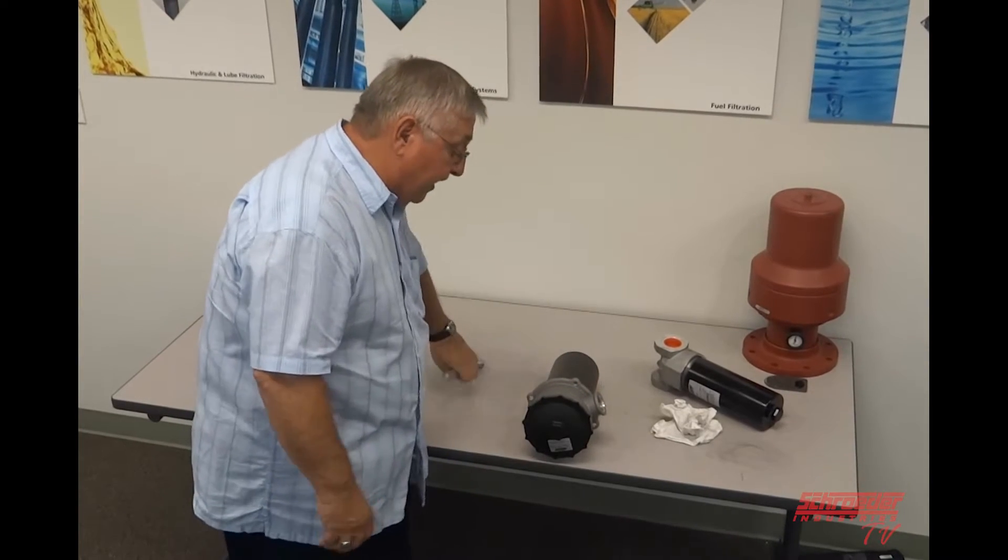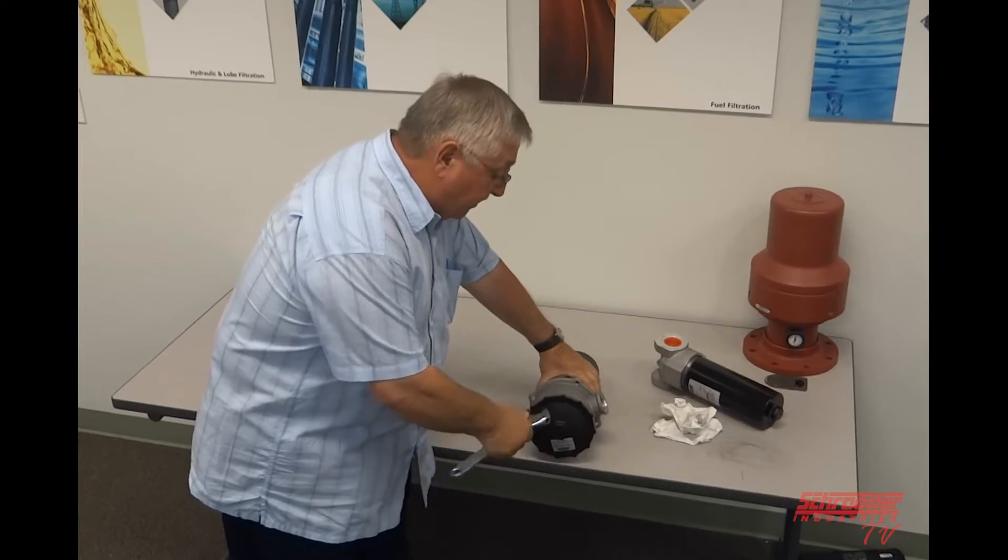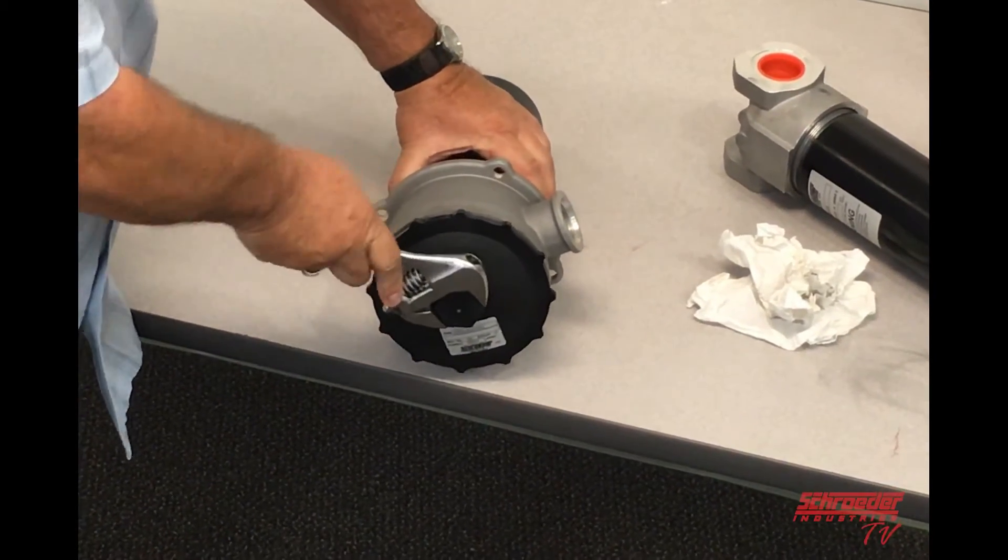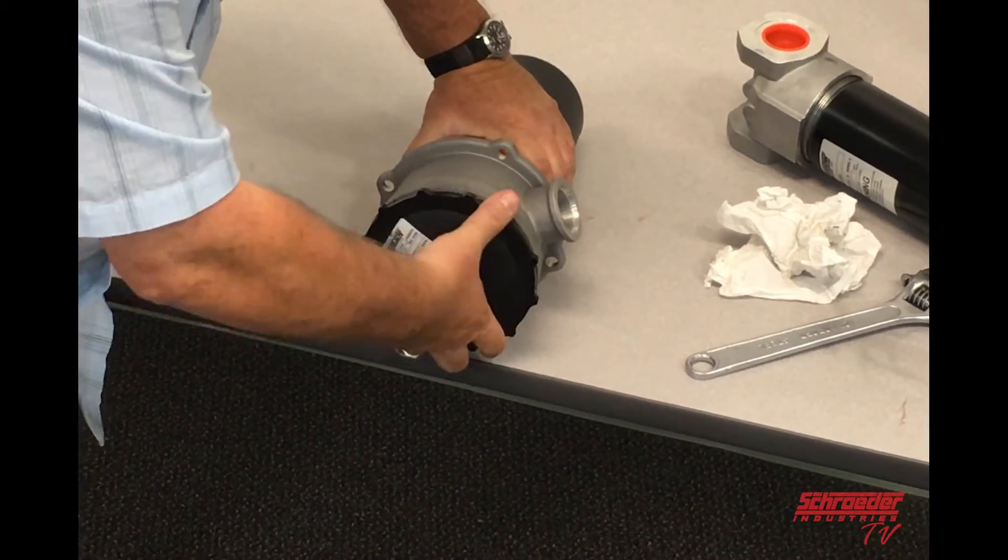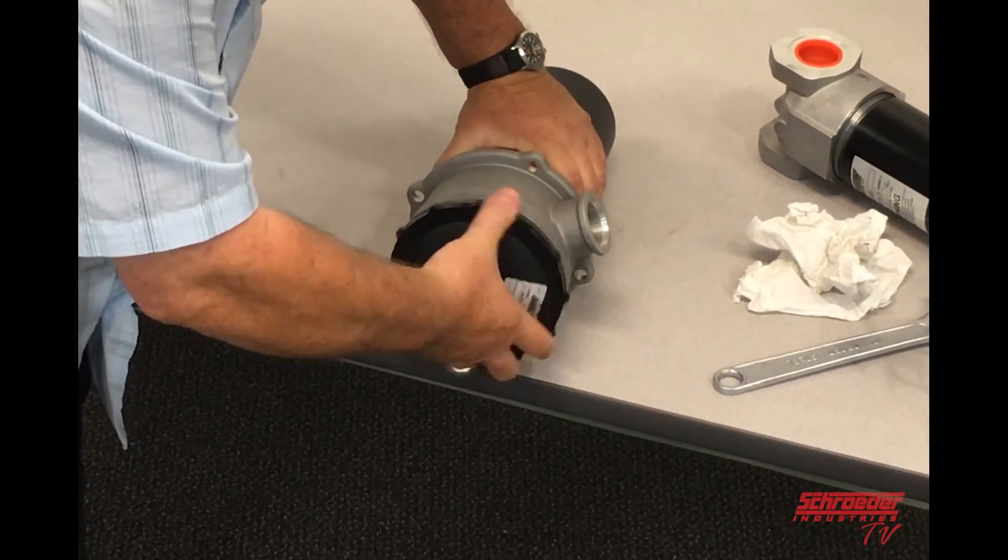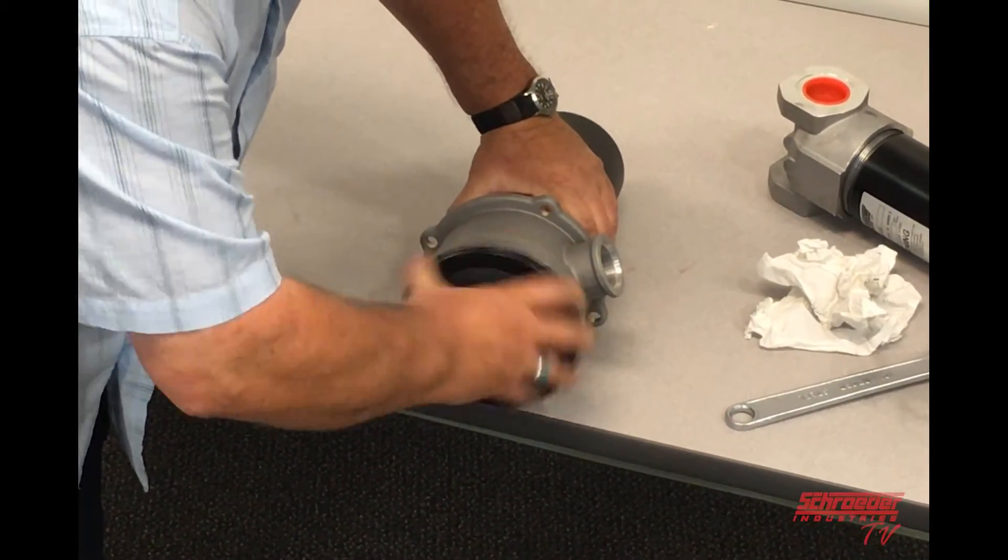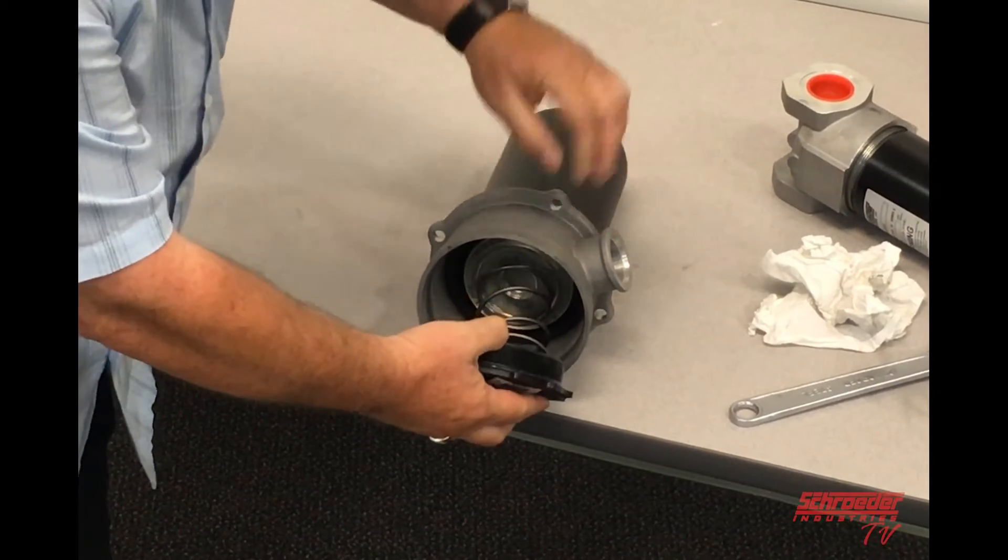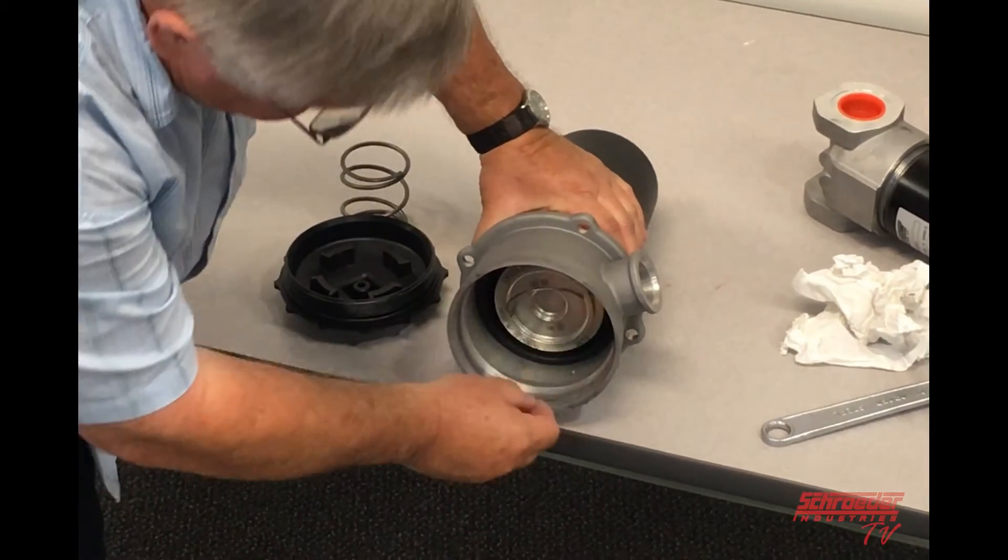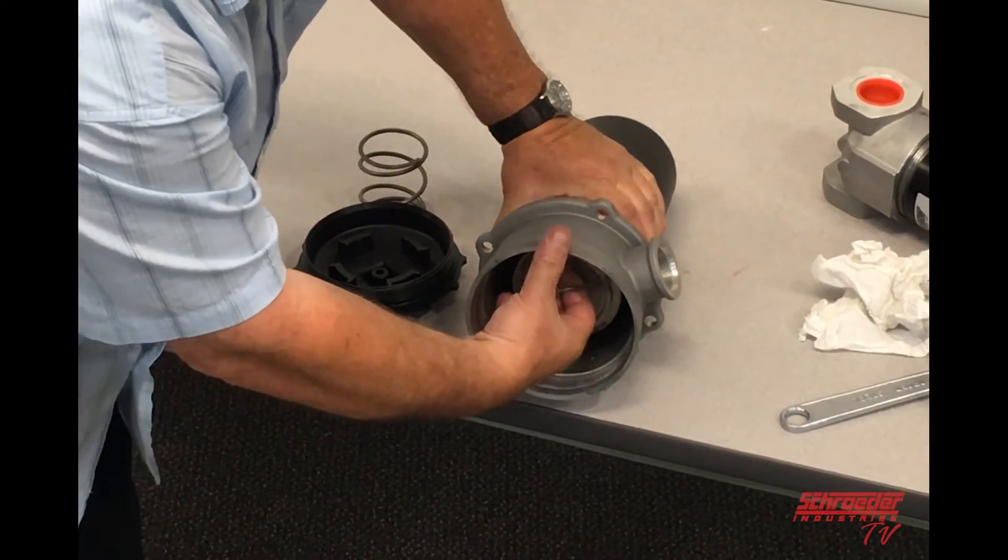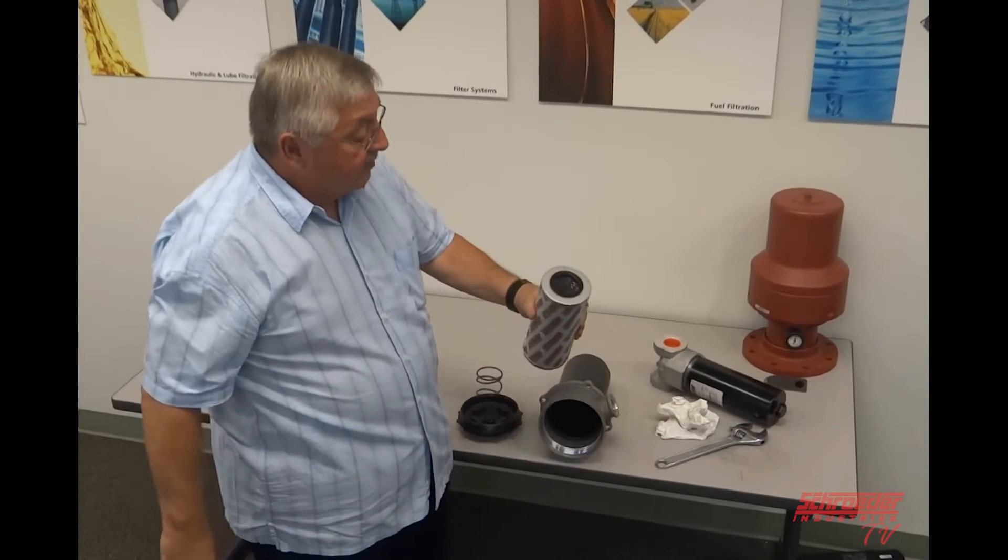This cap needs to be unscrewed. Again, it's got a hex on top of it. You need to find a crescent wrench or an open end or a socket, whatever you have. Turn the head here counterclockwise and just unscrew the head or the cap from the head very simply like this. As you notice, we've got the cap and there's a spring inside that holds the element. You reach in here, there's a little bail on the element, and you can pull the element off the guide tube that's in there and you replace this element.